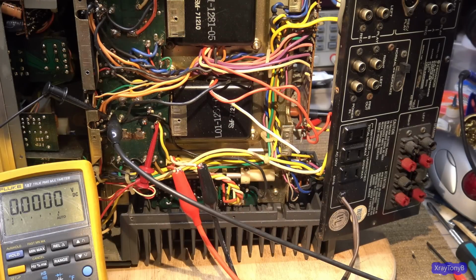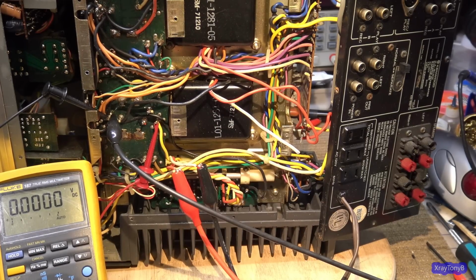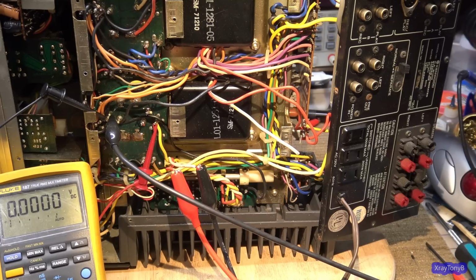But there's a fuse right in line with that, and the fuse in there was good, and it was the correct value, which is only like a 1 amp fuse. It's not a very large fuse. Actually, it's a 2.5 amp fuse. So you would think that the fuse would have blown before the transformer fried. The only thing I could figure is at some point in time, somebody replaced it with an incorrect fuse value.